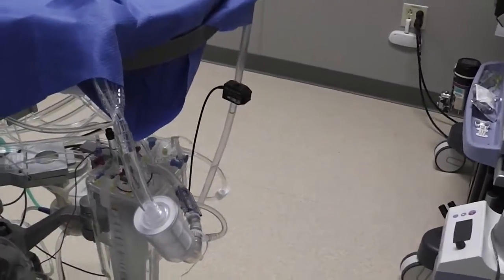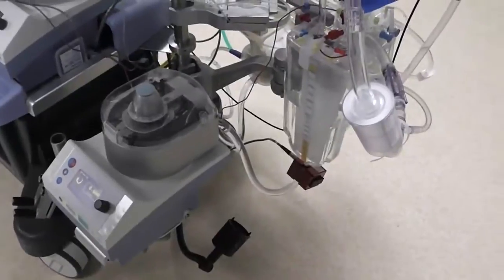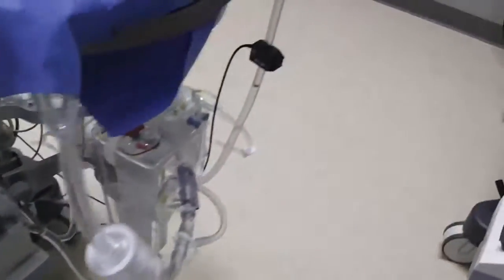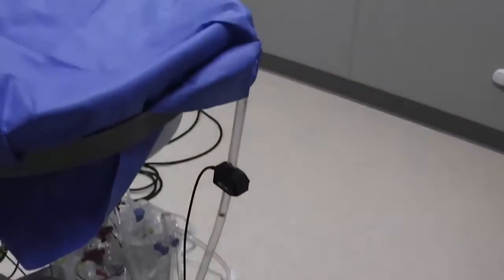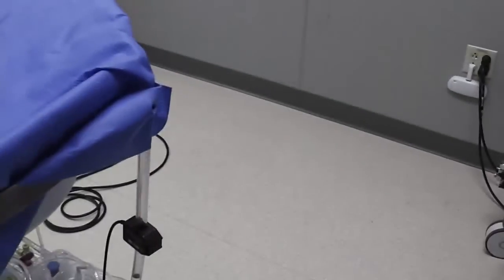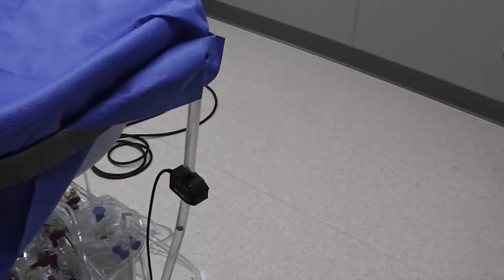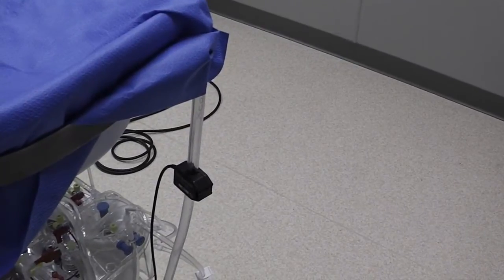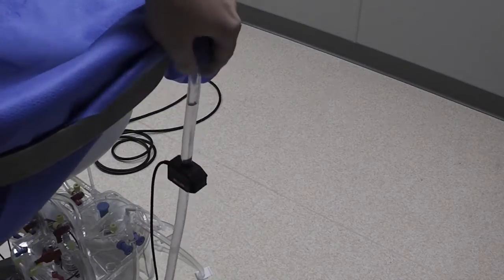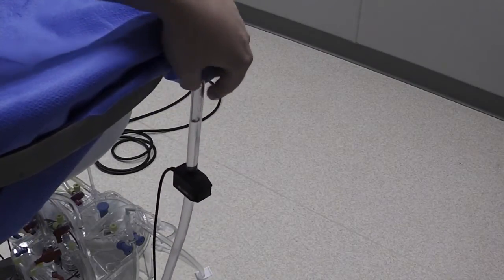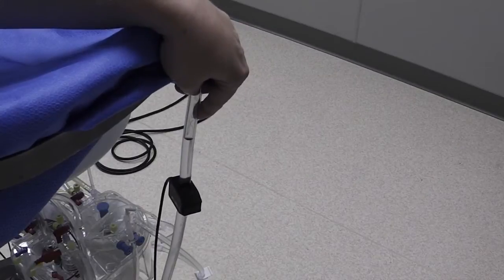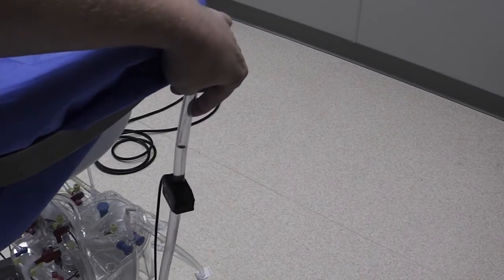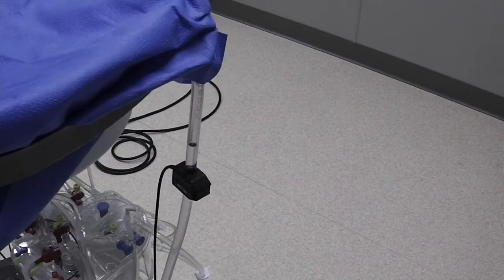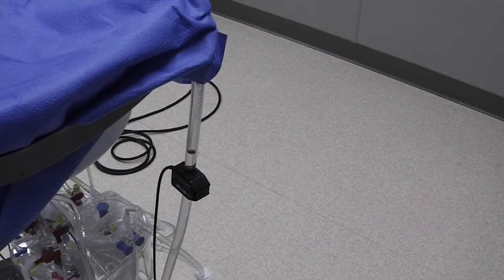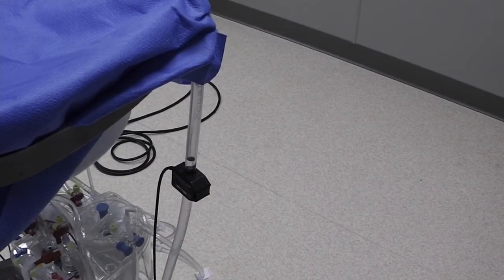And I want to stop the pump at its most occlusive setting with fluid coming up that line. So I'm going to give this one more turn here. You want this as high up on the line as you can get it. I'm sure you're probably aware by now, but in reality you want this to be 30 inches above the raceway, and you want to set the occlusion so that you get a 1 centimeter drop per minute, which, as you can see here, this is much faster than that.